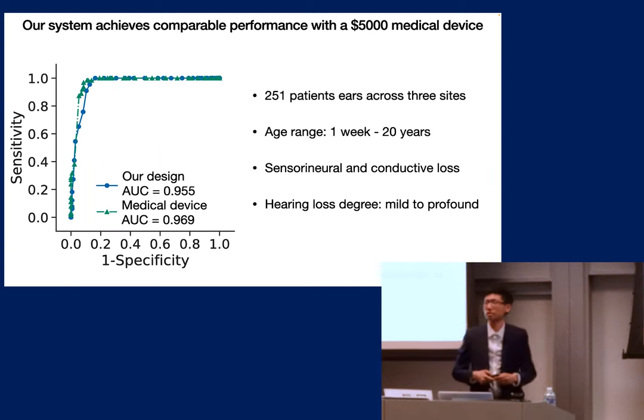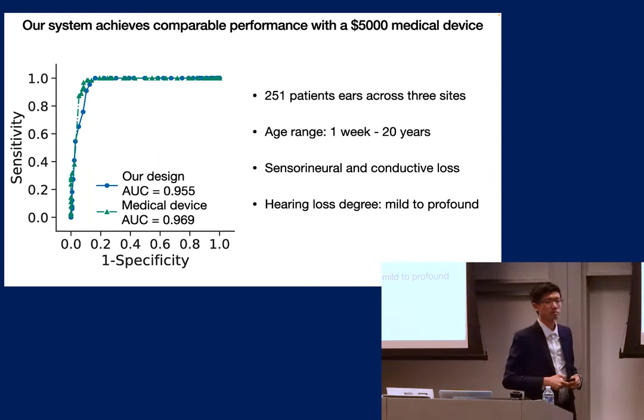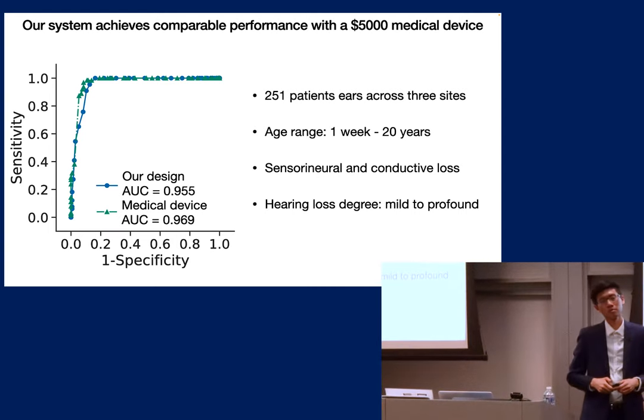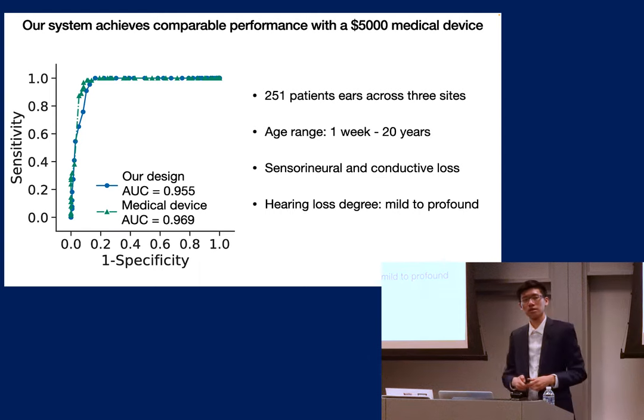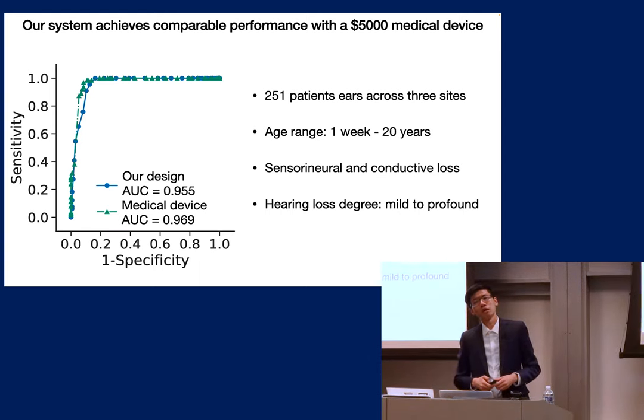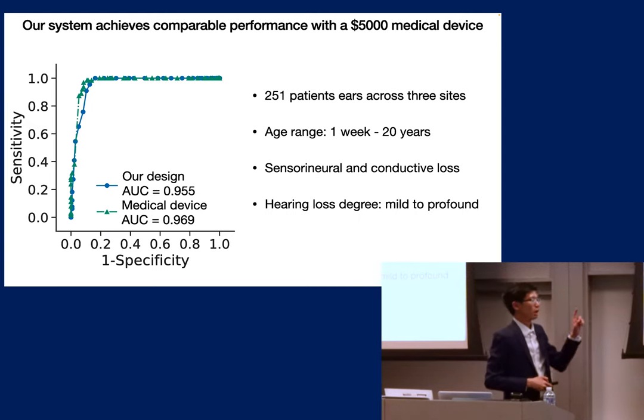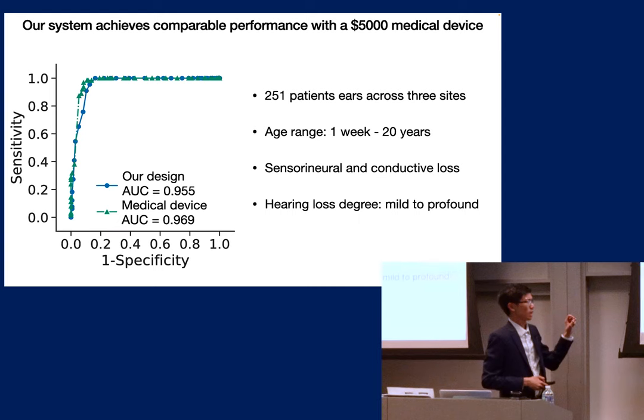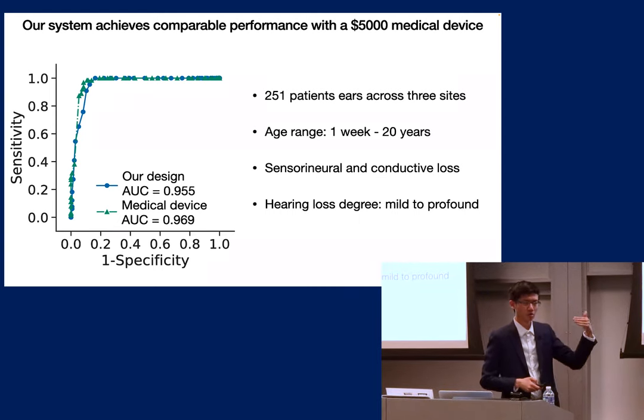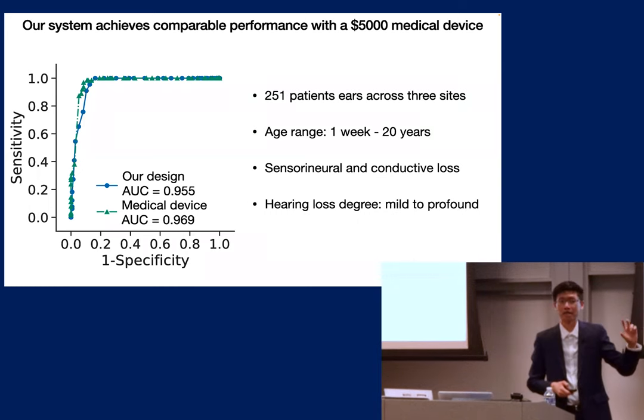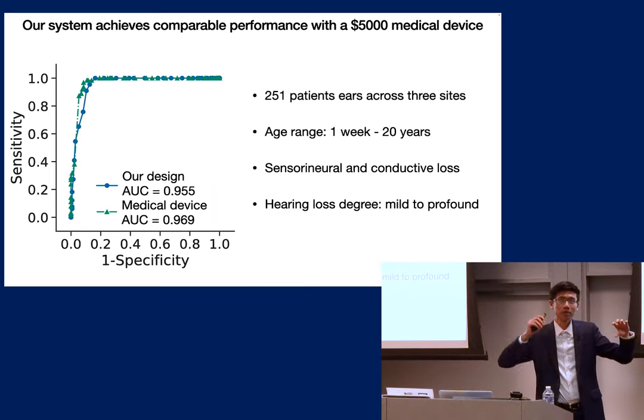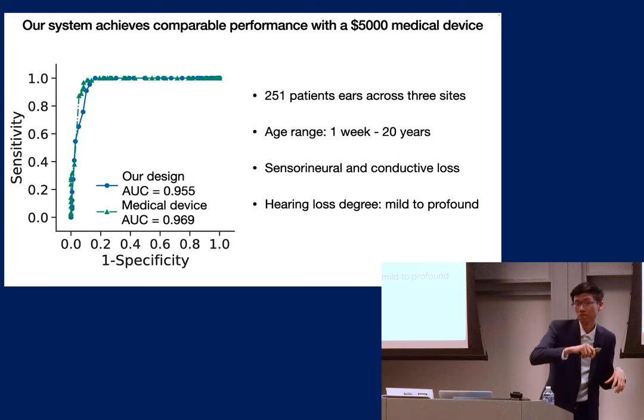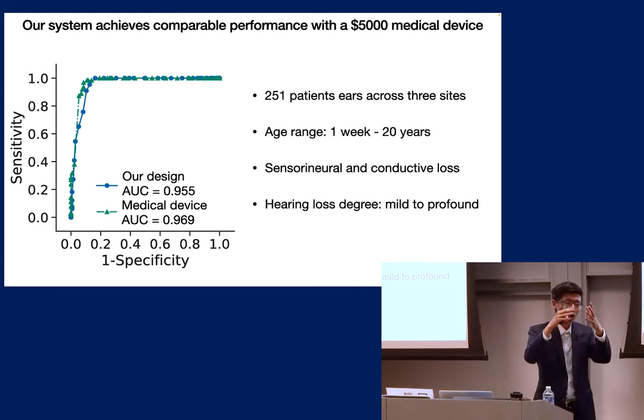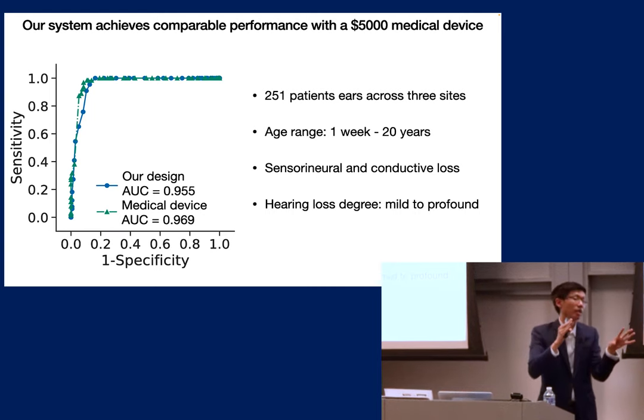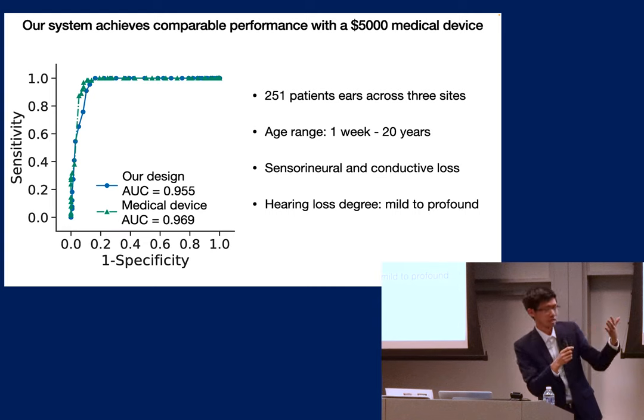It's not above the ADC range, but to give you an idea of the magnitude of signals coming from the cochlea, those can be negative 10 to 10 dB SPL. And 0 dB SPL is the limit for human hearing, so that's pretty low. Normally the transmitted signal you send in is about 80 dB SPL, so the reflections that come back could be anywhere from 80 to 60 to 50, within that range—which could overwhelm that 0 dB SPL signal coming from the cochlea.